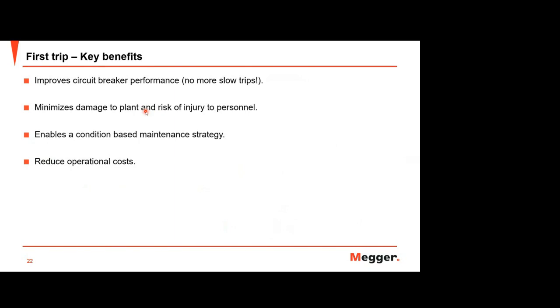And it also improves your circuit breaker performance. No more slow trips, as we expect, because you can detect early if you have this issue. And it also minimizes damage to plant and risk of injury to personnel. There is still a chance to injure a person, but if you follow the standard procedure for how to connect, it will be safer compared to conventional testing, because that takes more time and carries more risk. It also enables a condition-based maintenance strategy, which is now trending. It will reduce your operational costs because you don't need to spend a whole day doing maintenance on your circuit breaker. These are the first trip key benefits I can share.